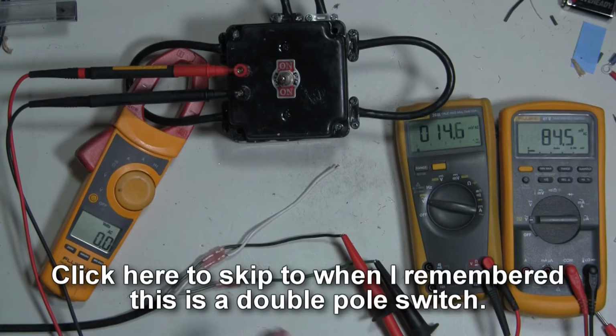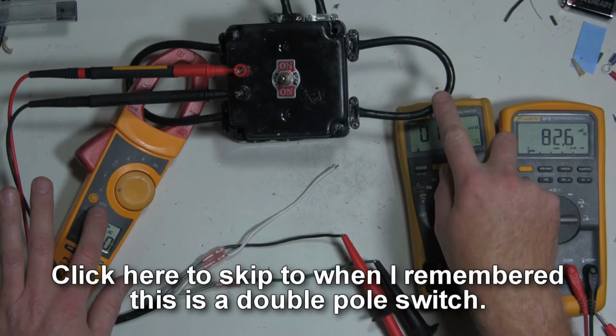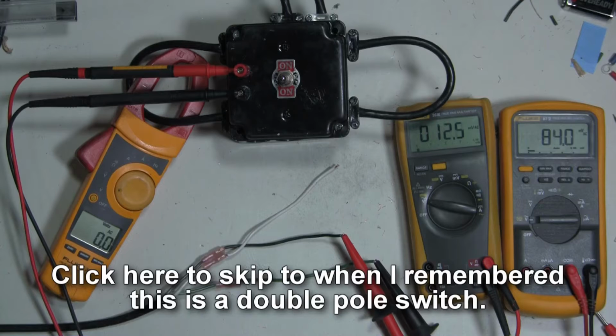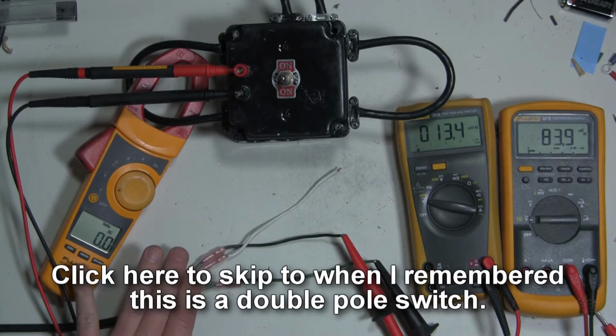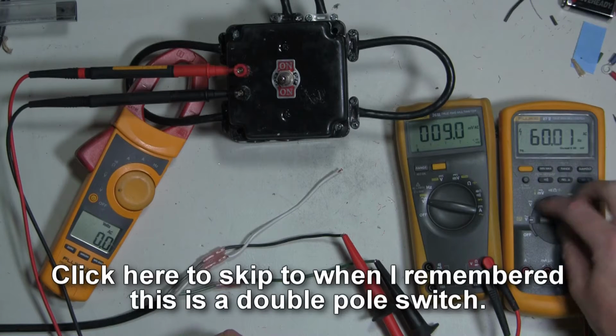So now that we've got everything electrically connected, I want to test the circuit before I test it with a load. So I've got an example of how this would be set up, with the exception of you would most likely only be using one voltage reading and possibly two current readings. The only reason why I have this meter set up is to measure the outgoing current, just to see if electrically it's working, if it sends current actually to the legs of this cable that we expect it to, and make sure that there's nothing else that's faulty. So again, this would not be used.